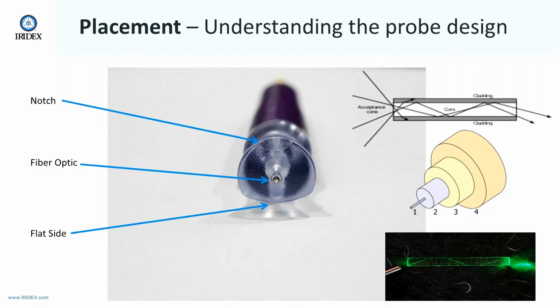Understanding the probe design of the MicroPulse MP3 probe. The fiber optic, which you see, is offset 2/3 to one side of the probe and 1/3 to the other side of the probe. This is what makes it crucial that we have it oriented in the proper format. The fiber is also called a bubble fiber. To produce this, we must heat the fiber optic, which in turn will remove the insulation factor. If you look at the way light and its indices moves through the fiber, it doesn't move in a straight line.